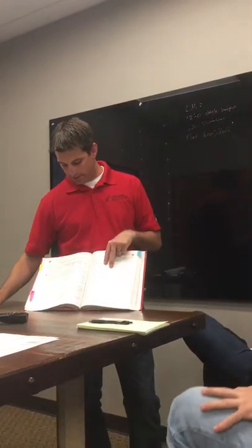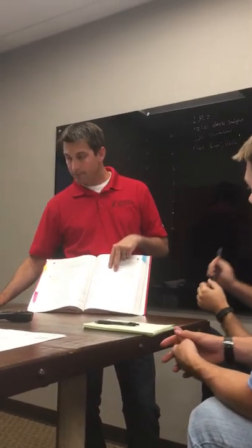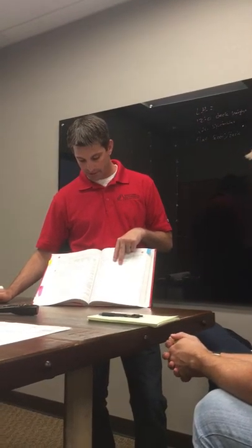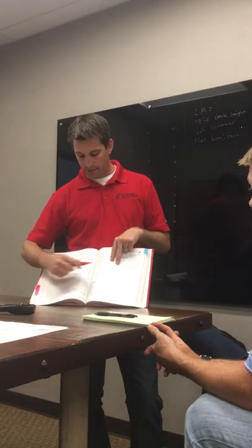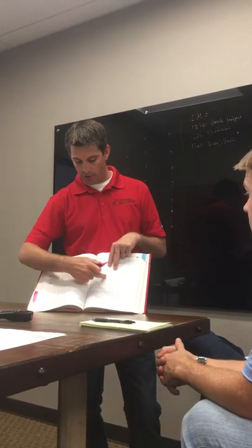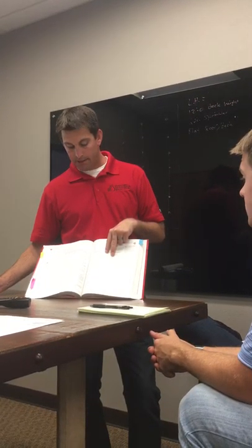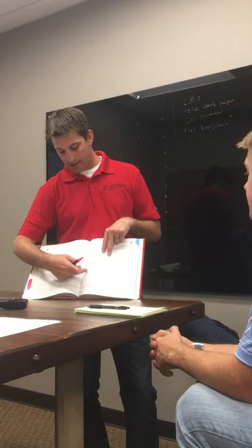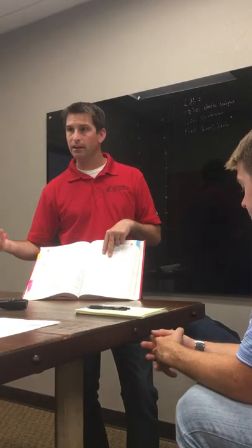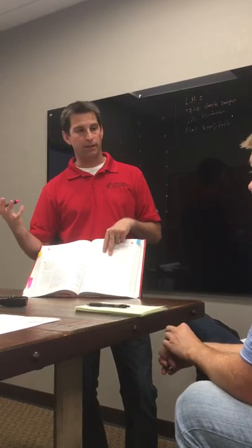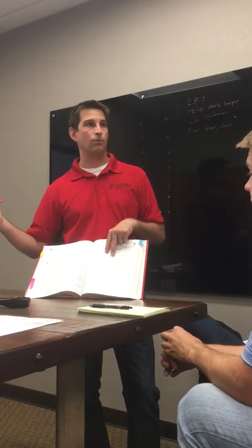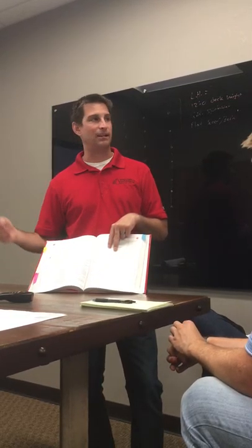What's ordinary one? 0.15 at 1,500. What's ordinary two? 0.2 over 1,500. And then what about extra hazard? We get into extra hazard group one: 0.3 at 2,500. It's up, and you can't even go down to that spot. You have to go at least that, because they're saying the fire is going to grow real fast, burn really hot, and trigger way more sprinklers. So you have to do this big area.